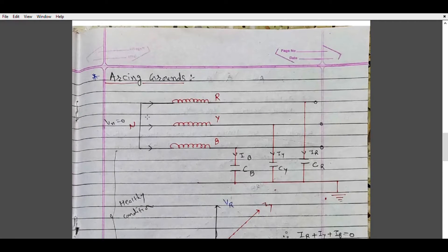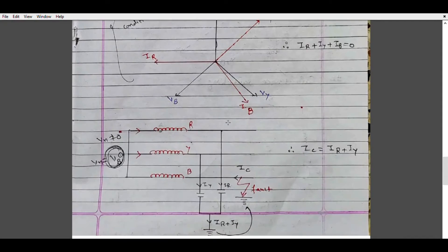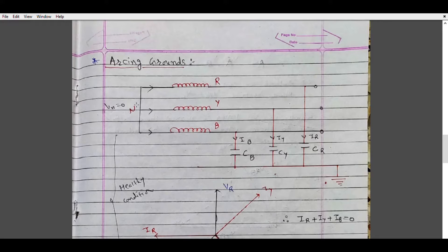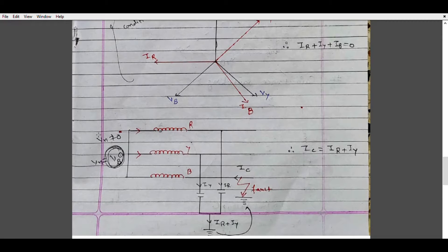The direction of current in the healthy phases remains the same as before, but in the faulty phase the direction of current is reversed. Initially the voltage at neutral was zero, but now due to the line-to-ground fault in the underground cable — where the neutral is not grounded — the voltage at the neutral is no longer zero. So Vn is no longer zero; Vn is now equal to Vb.